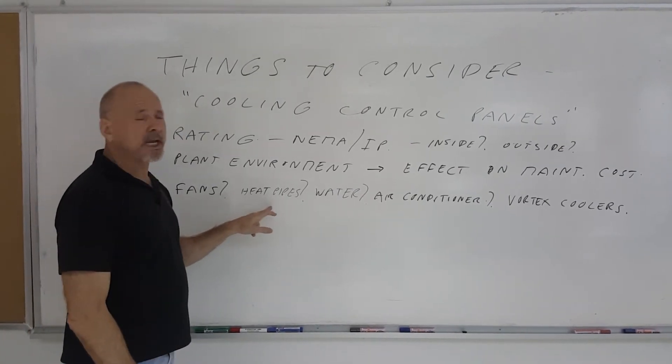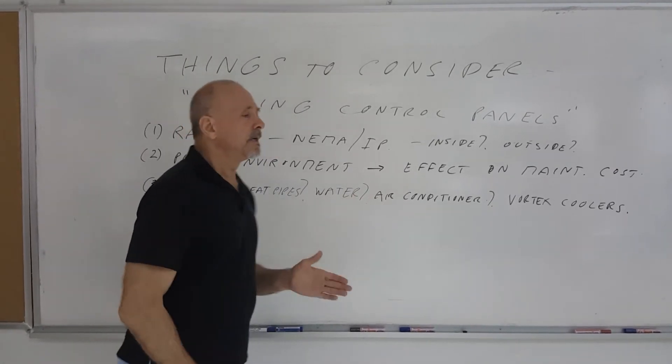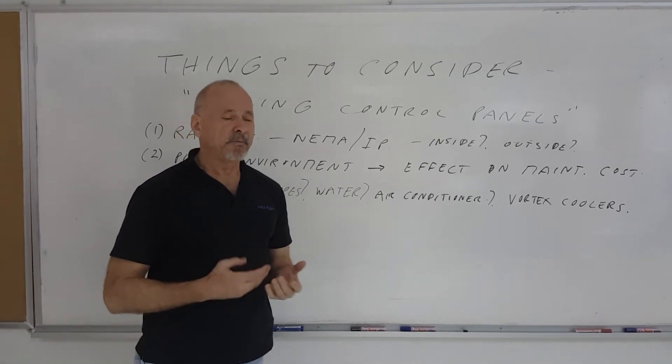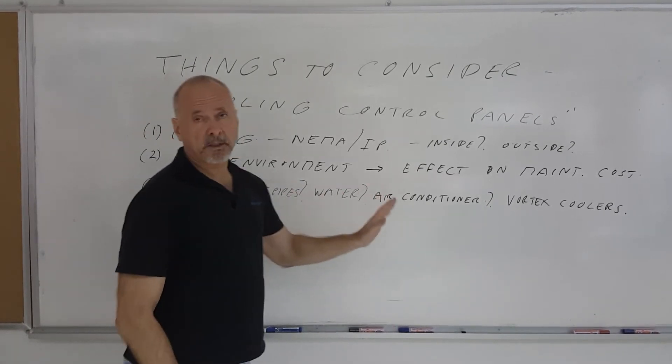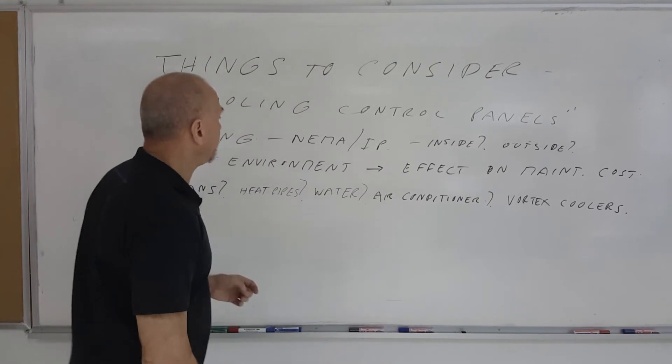Heat pipes are a nice way to take heat from the inside of a panel out. But heat pipes cannot reduce the temperature to below what the ambient is. If the ambient temperature in the factory is very high, you're better off to go to an air conditioning or a vortex cooler system to cool the control panel.